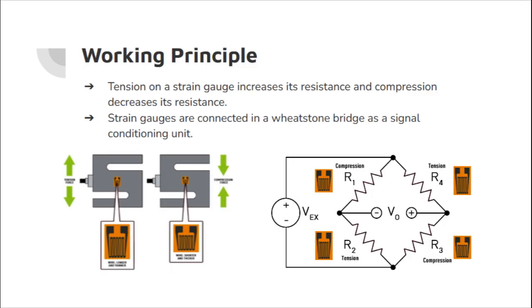Now let's see about the working principle of a strain gauge based load cell. Tension on a strain gauge increases its resistance and compression decreases its resistance. These strain gauges are connected in a wheatstone bridge which acts as a signal conditioning unit.